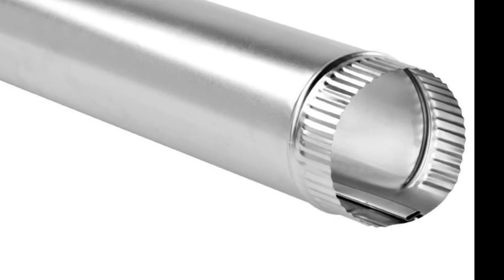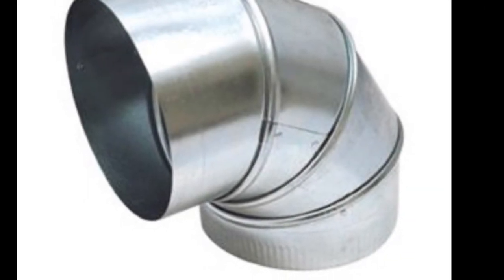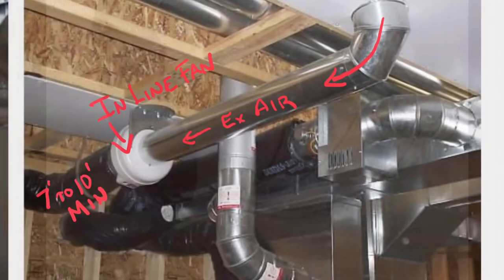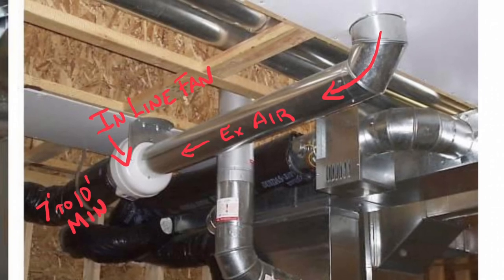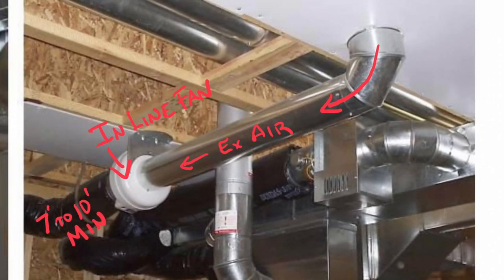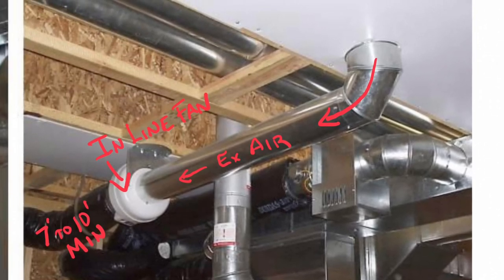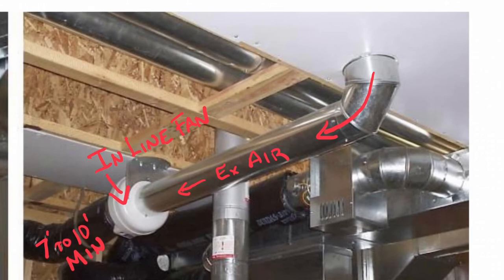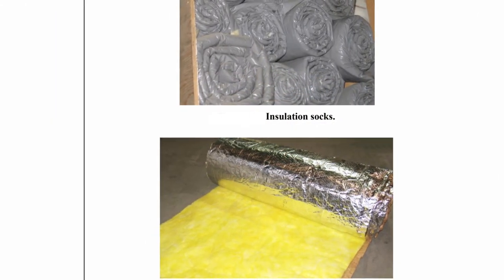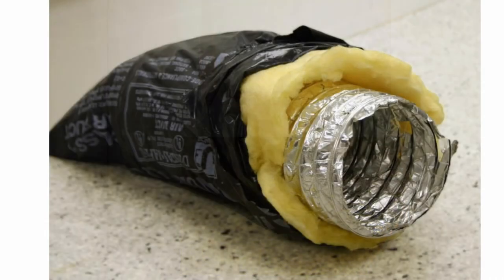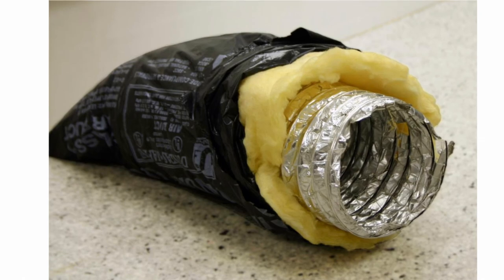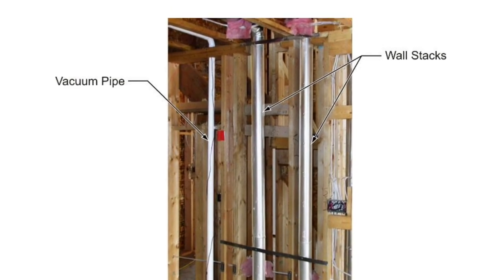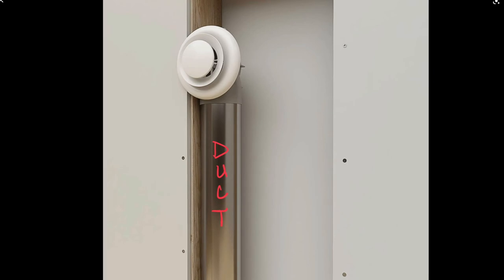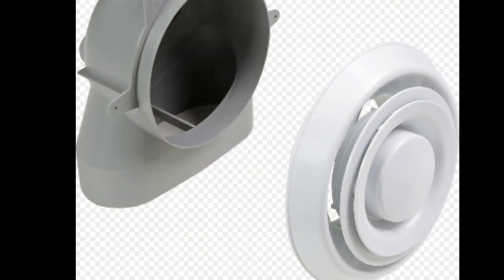Most of the exhaust systems will be using round pipe and round elbows. This illustration shows an inline fan exhausting air from the dwelling with insulated flex going to the outside. This insulated flex or insulation over the pipe should be for the first 7 to 10 feet from the exterior wall. This will help eliminate condensation on the exterior of the pipe during cold periods of the winter time. In most cases, our exhaust systems are installed with round duct, stack heads, a plastic stack head, and a round diffuser.